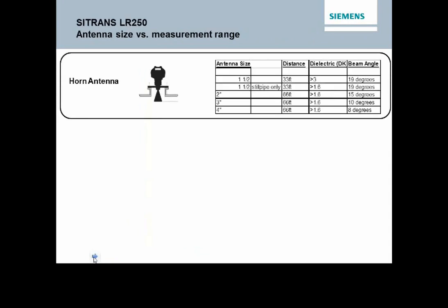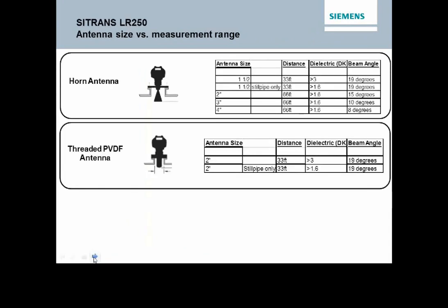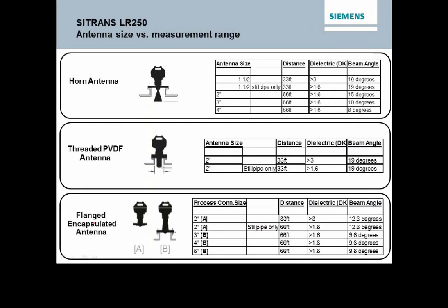We went into a little bit on this already, but to give you a little better feel for this, today we're talking about more of our hygienic or flange encapsulated antennas. Two things come into play here. One, based on the antenna size. If you take a look here, in the smaller 2-inch connection size, we're looking at a distance of 33 feet being the maximum available. As we get into larger sizes, we have a stronger beam and can measure greater distances.